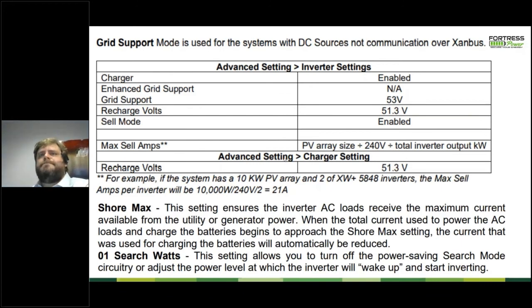Let's see. Grid support mode, that's selling back to the grid at a high voltage. These are going to be customer specific settings. Some customers don't want to have a grid charge. They just completely disable the grid charge and wait for the sun to come back up. What we suggest is setting your recharge voltage right around our nominal voltage of 51.3 to 51.2. That'll be around an 80% depth of discharge, or 20% state of charge, so that the battery just operates from its 20% range to its 80% range on a regular basis.